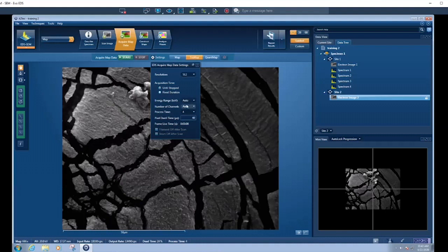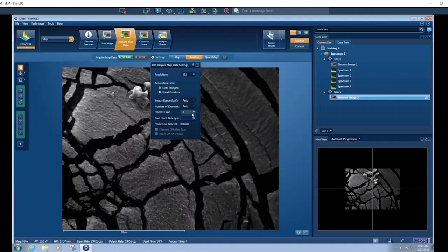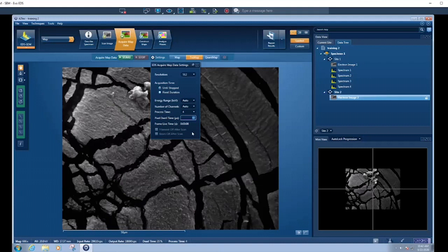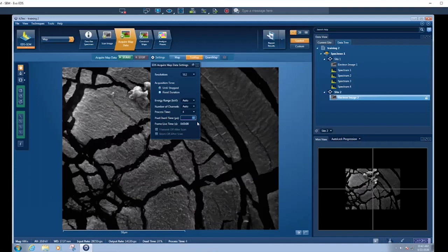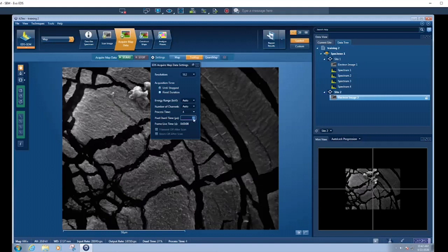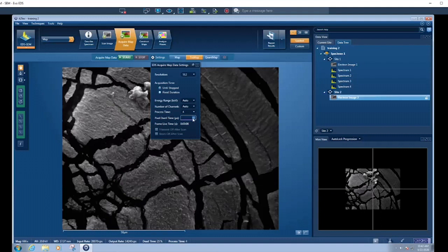The energy range, again auto. Number of channels, auto. Process time, same as what we've chosen before. The pixel dwell time, this is an order of magnitude less than what we were talking about for our point and ID. That's always important to remember that each pixel will have an order of magnitude less information than our point and ID. This is really about trying to create enough signal that we can differentiate between different regions. But if we want to have enough signal that we can quantify specific pixels or a few pixels, then we need to count for a very long time.